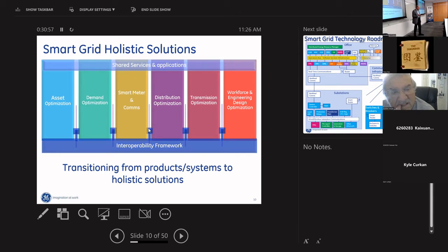Transmission optimization today focuses more on synchrophasors. There's a big difference: typically the data we use is 2 to 4 to 6 second data, called SCADA data, Supervisory Control and Data Acquisition System, sampled at the rate of the master station and control center. But with phasor measurement units, we're getting maybe 50 samples per second, which gives us a lot more granularity and insight into the grid.